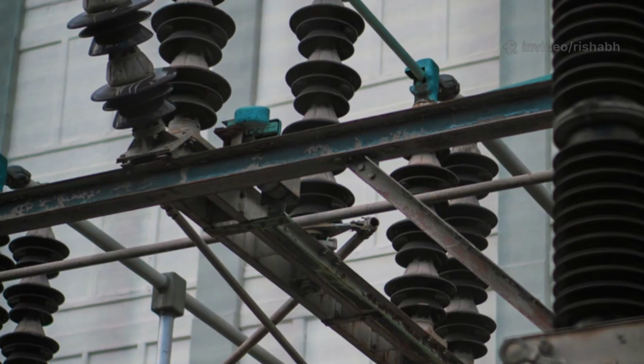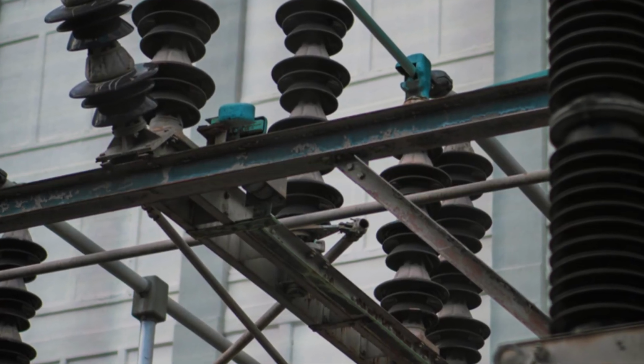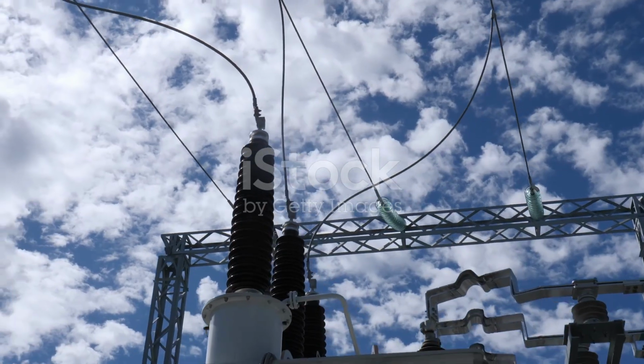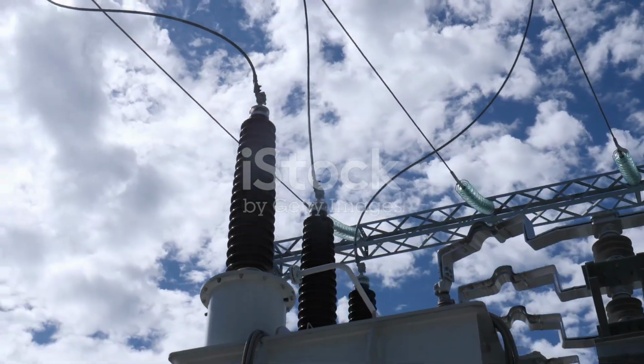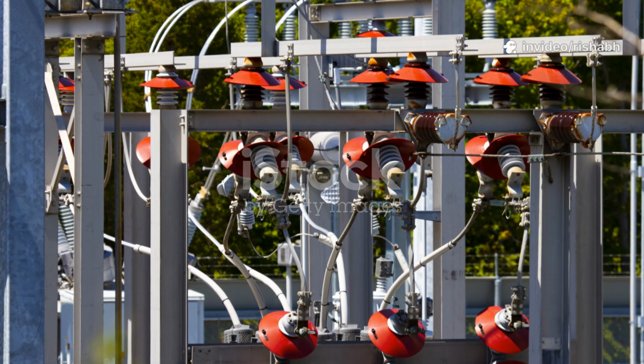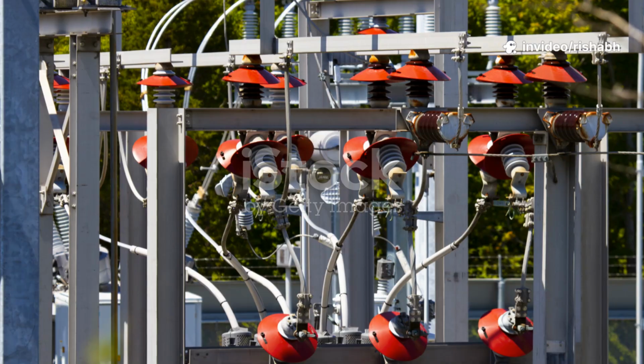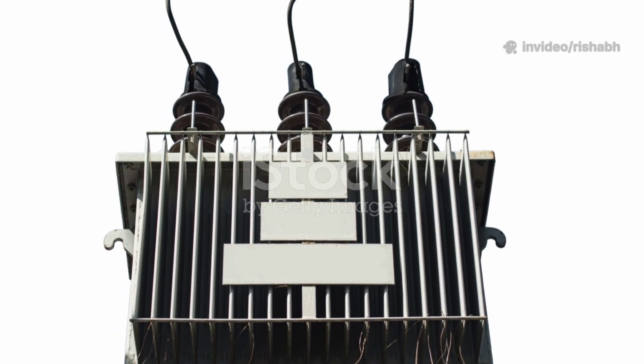The solution is a specialized insulator called a bushing. A bushing is an insulated conductor that provides a safe passage for the current to travel through the grounded barrier of the transformer tank. It is the carefully guarded gateway between the transformer's internal world and the external grid.